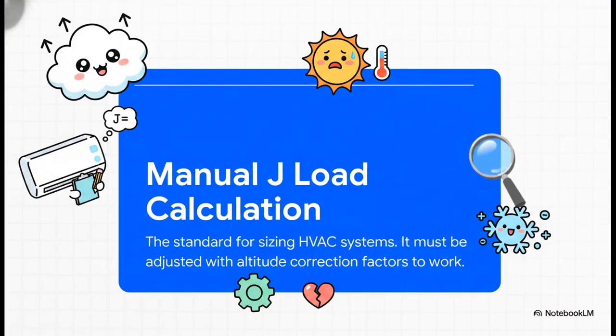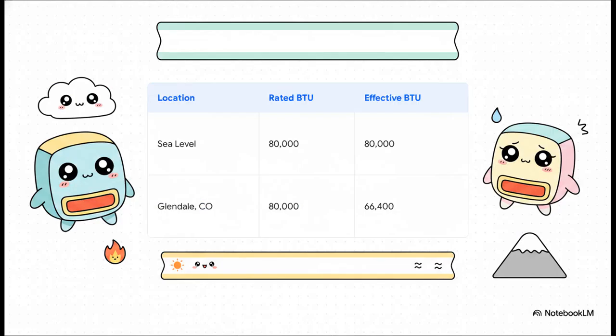A key tool for this is something called the Manual J load calculation, the formula technicians use to figure out exactly how powerful your system needs to be. But here's the catch: if you don't apply specific altitude correction factors to that formula, the calculation is completely wrong. And that leads to systems that are either overworked or constantly shutting themselves on and off until they die. The difference is stark. A furnace rated for 80,000 BTUs of heating power at sea level, in Glendale's thin air, is only going to produce about 66,000 BTUs.